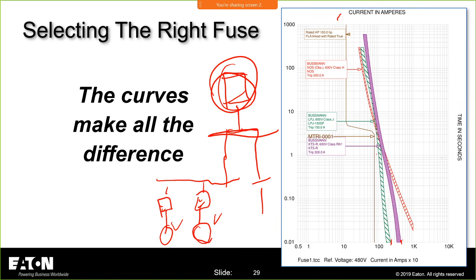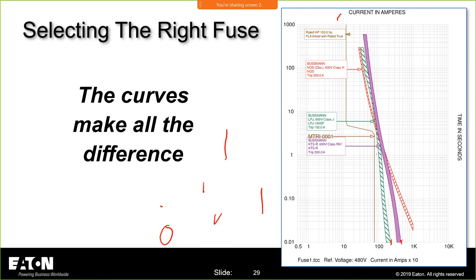So there are some general rules of which class fuse you'd want to use. If you have heavy motor loads in your system, you may want a time delay fuse, something that gives you a little bit of time delay as opposed to a fast acting fuse, just to give you some ride through on motor inrush currents and things of that nature. But when you're down close to the loads, on the primary of a transformer, right there at the motor, you're going to be considering these devices.